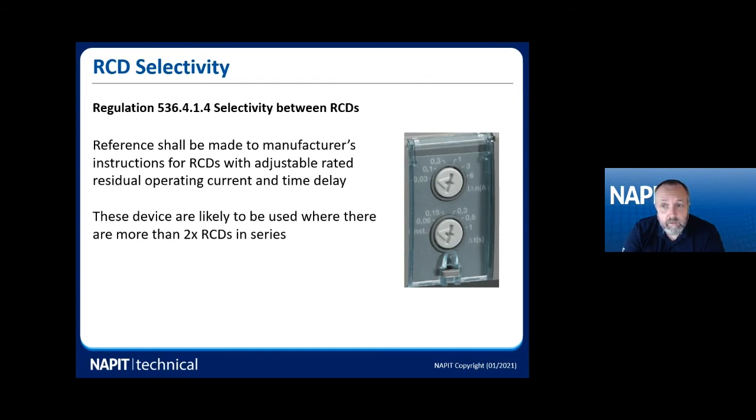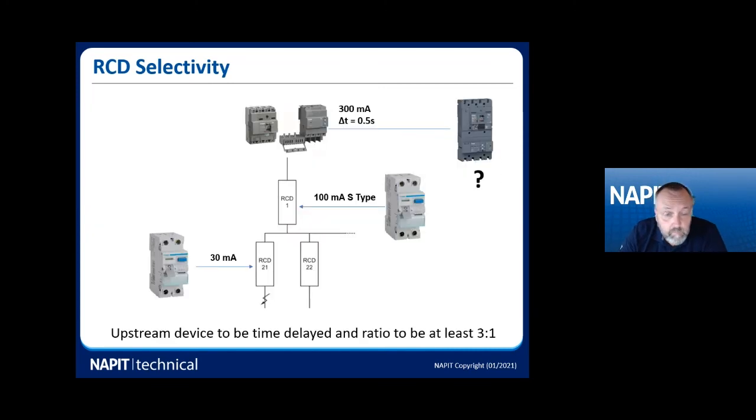Really very complex piece of equipment, and we're going to bring the guys back again in a minute, but on an EICR, please bear in mind that those have already probably been set for a particular reason, and it's not a good idea to be going and tweaking them unless you've essentially found out before you tweak them what they should be. So when you're doing EICRs, just remember that you've got to almost try and get your head around these designs in case you come up against any of this kind of equipment we're going to talk about next, because you will have to code it and you will have to maybe tweak it for the owner if someone set them incorrectly.